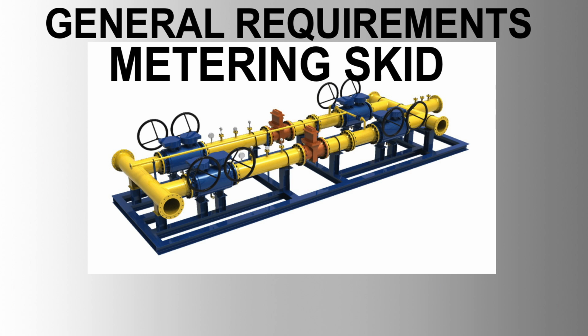Electronic data, meters should support HART or Modbus communication protocol for configuration and diagnostics. Output signal should be a standard 4 to 20 milliamperes with digital signal superimposed for HART communication.